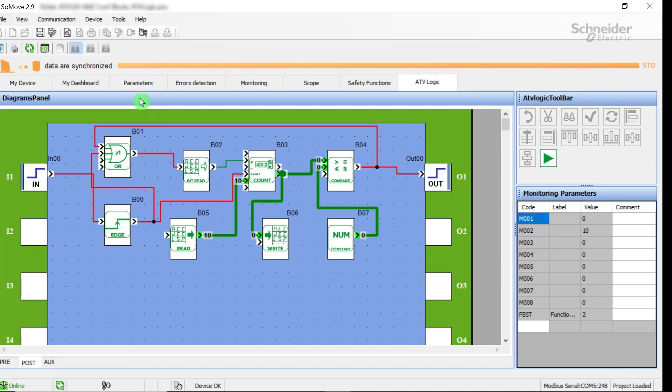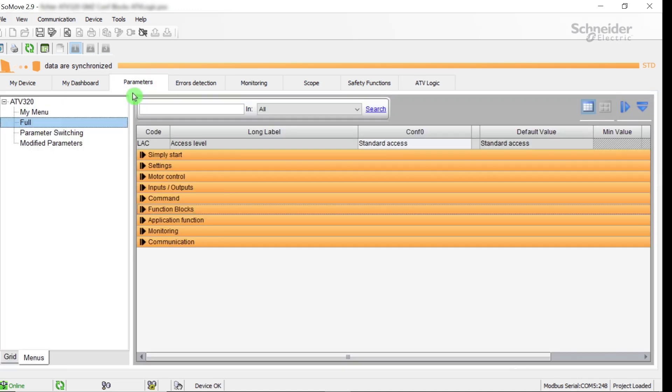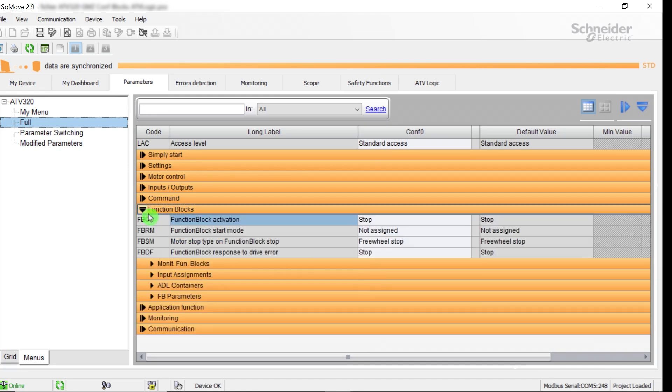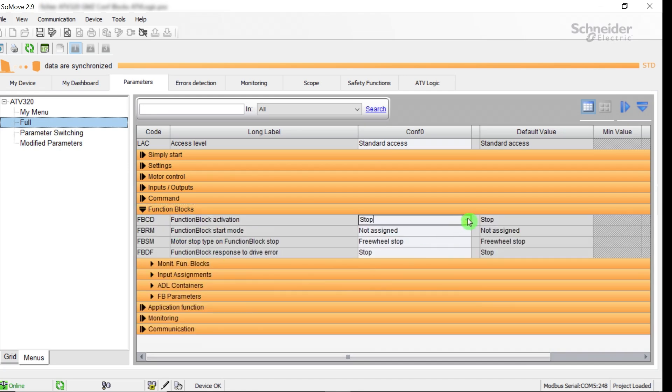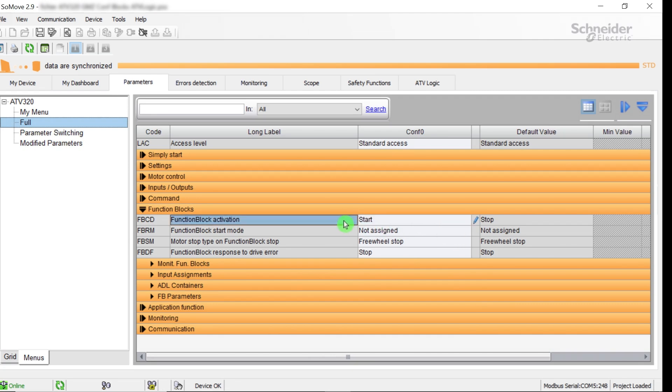The program task is managed by parameters to start and stop upon ATV320 power on. After downloading, to execute the program, you should set the function block activation parameter to start for testing. To be more efficient, we recommend the following parameters on operational modes of the ATV logic task: FBCD, FBRM, FBSM, and FBDF parameters in the Function Blocks tab.